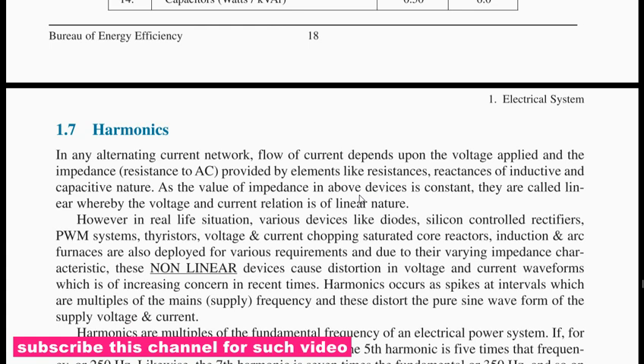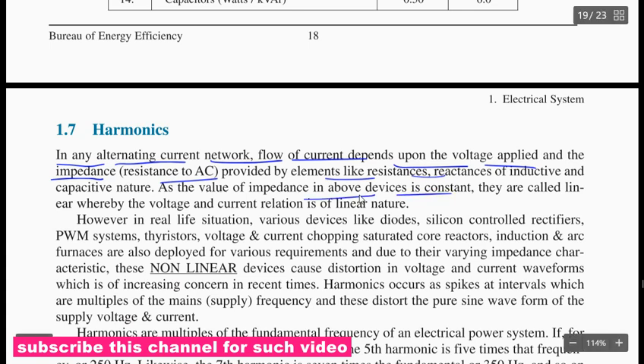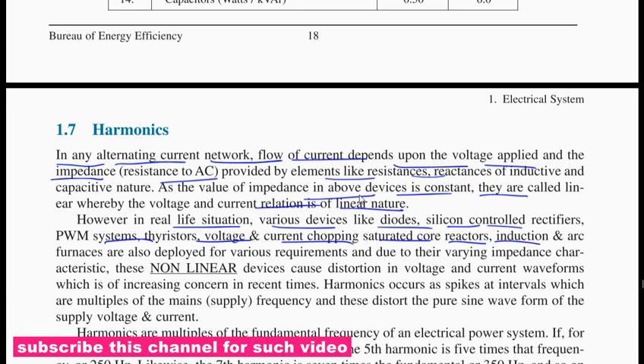Let's talk about harmonics here. In any alternating current network, the flow of current depends upon the voltage applied and the impedance, the resistance to AC provided by elements like resistance, reactance, and the inductive and capacitive nature. As the value of impedance in the above devices is constant, they are called linear, whereby the voltage and current relation is linear in nature. However, in real-life situations, various devices like diodes, controlled rectifiers, SCR, PWM systems, thyristors, voltage control choppers, saturated core reactors, inductors and arc furnaces are also deployed for various requirements. Due to their varying impedance characteristics, these non-linear devices cause huge distortion in voltage and current waveforms, which is an increasing concern in recent times.